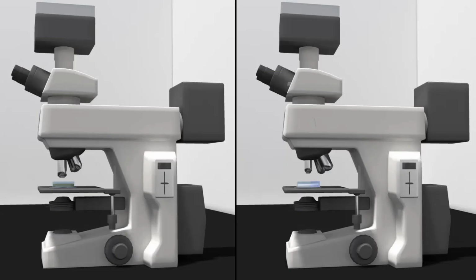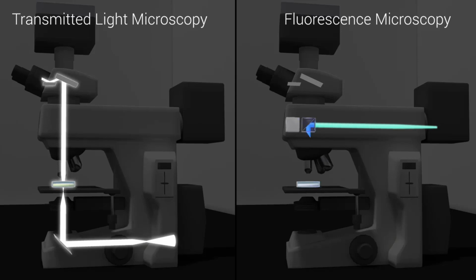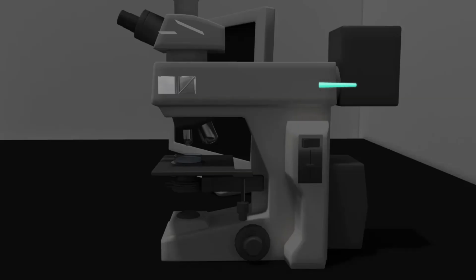In a fluorescence microscope, the light source travels in a different trajectory than in the basic light microscope that we illustrated in the microscopy experimental technique animation. Instead of the laser light being transmitted through the sample, as in a simple bright field-based light microscope, the fluorescence microscope uses incident or reflected light. From the laser light source, the excitation laser beam travels through the filter cube, which is used to provide the appropriate wavelength of light to excite the fluorescent molecules, or fluorophores, used in the sample, then through the objective to focus the laser light on the sample.